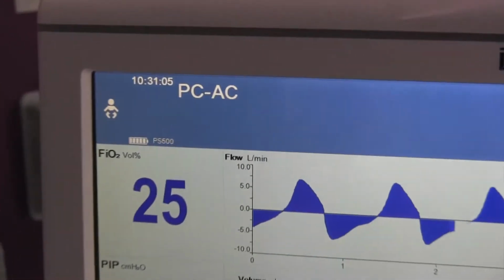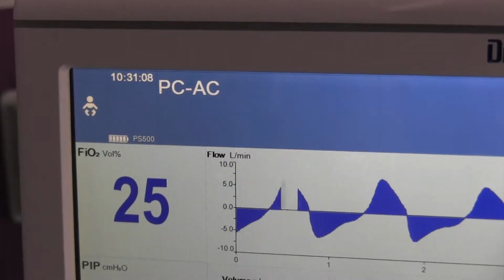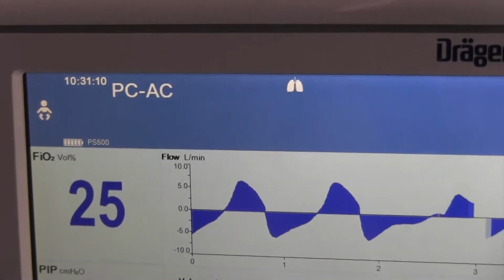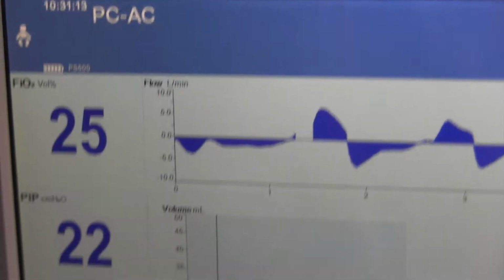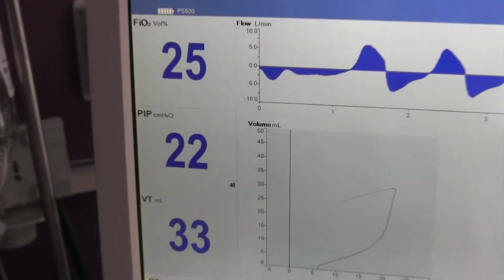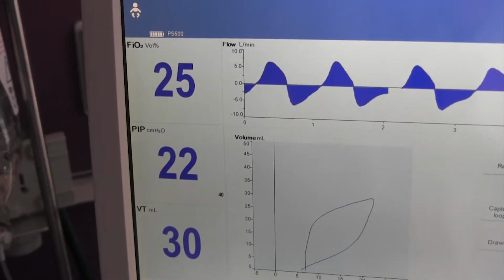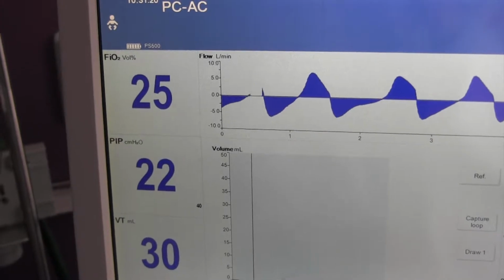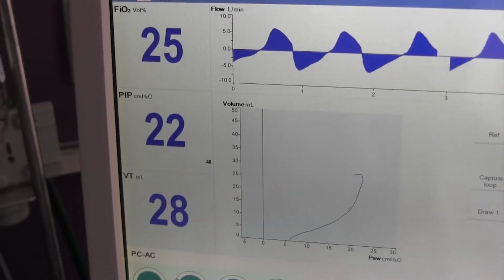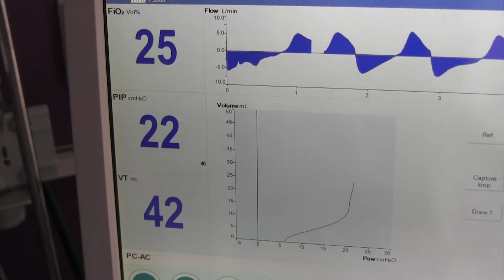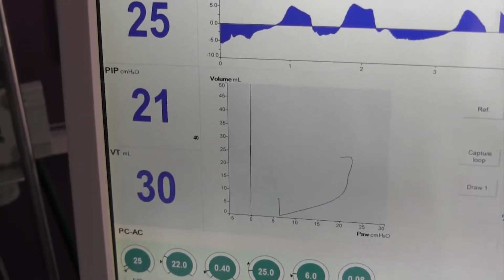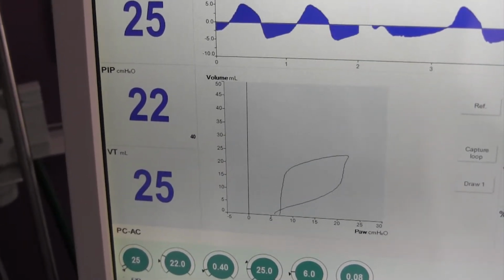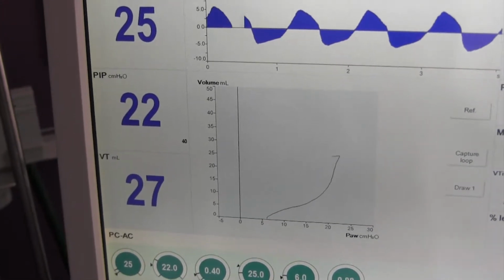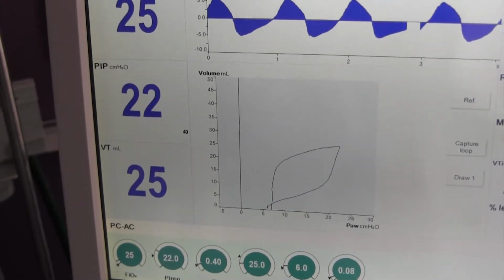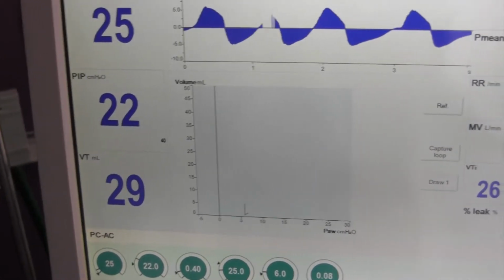If you look at the rest of the screen, up at the very top there, you'll see it says PCAC, so that's a pressure control assist control mode, so the mode that you're in will always be displayed up there. The ventilator will also give you some numbers across the side that tell you important things like, again, your fraction of oxygen inhaled, your peak inspiratory pressure, which you'll see changing from breath to breath here if you watch it for a minute, and then the tidal volume. So if you're in a pressure mode, you'll see a tidal volume displayed. If you're in a volume mode, you'll see that pressure displayed, so it kind of gives you feedback about how the patient's doing with the ventilator.